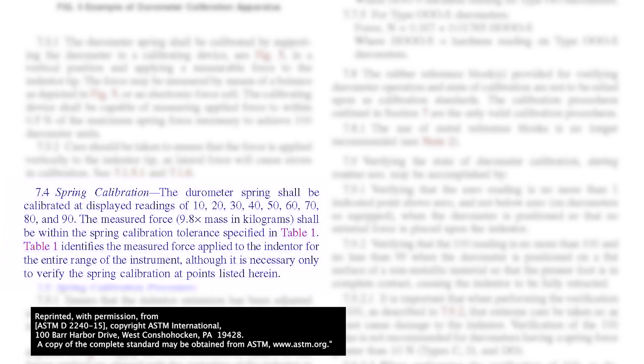If we take a look under section 7 of ASTM D2240-15, that covers calibration of the durometer itself. Under section 7.2.2, you'll see there is plus or minus one durometer unit at all other points delineated in section 7.4. In that 7.4 section, all of those different readings range anywhere from 10 up to 90. So as long as the durometer is within plus or minus one point at every one of those measurements, the durometer is in calibration and is valid for use.